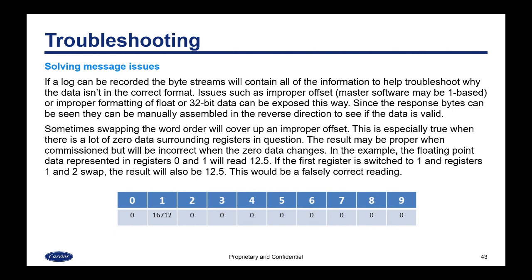Sometimes swapping the word order will cover up an improper offset. This is especially true when there is a lot of zero data surrounding the registers in question — the result may appear correct when commissioned but will be incorrect when the zero data changes. In the example, the floating point data represented in registers 0 and 1 will read 12.5 when put together. If the first register is switched to 1 and registers 1 and 2 are then swapped, the result will also be 12.5 — but this would be a falsely correct reading, and if the zero data in register 2 changed, you would not be reading the correct information.